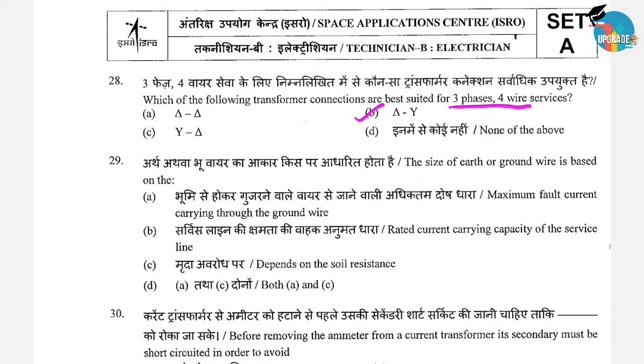The size of earth or ground wire is based on: A) maximum fault current carrying through the ground wire, B) rated current carrying capacity of the service line, C) soil resistance, D) both A and C. Correct option is D, it depends on the maximum fault current and also on the soil resistance.